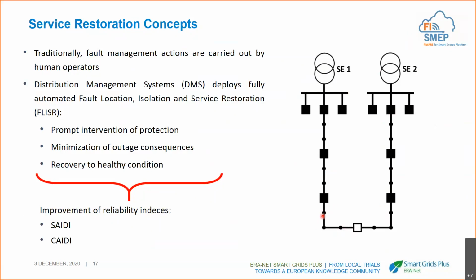So the point is that in the unfortunate case of a fault that occurs in the grid, we have to isolate this fault by opening the upstream circuit breaker, the upstream switch, and opening the downstream switch. In this way, we have isolated the fault, but consequently, the loads that are downstream are now de-energized, so they are not connected anymore. They don't receive energy anymore. What we have to do is to close what we call the tie switch, so the normally open switch, which is in the middle.